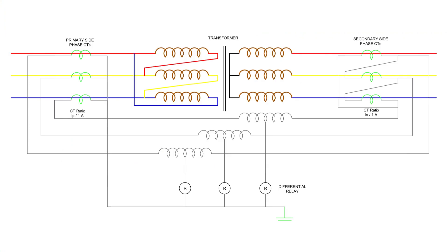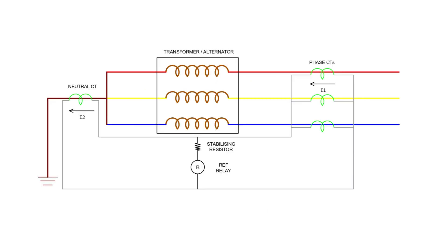Moving on to differential current protection. This type of protection involves relays that compare phase currents on either side of the transformer. If the differential current surpasses the set limit, the relay sends an operating signal. This safeguards the transformer from winding short-circuit faults and interturn faults. Lastly, we have restricted earth fault, or REF, protection.